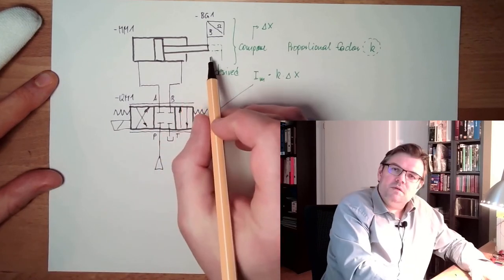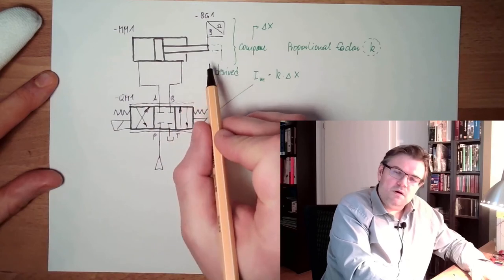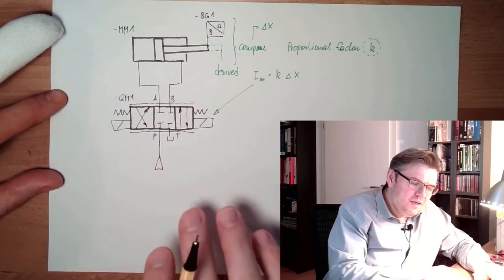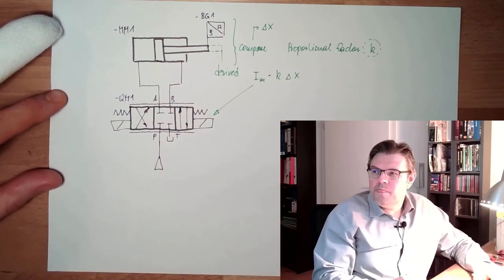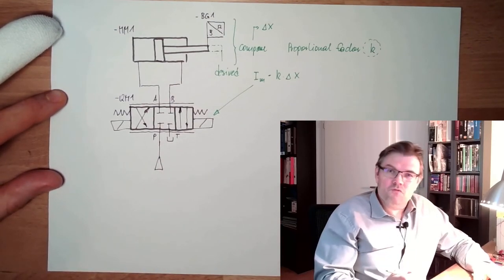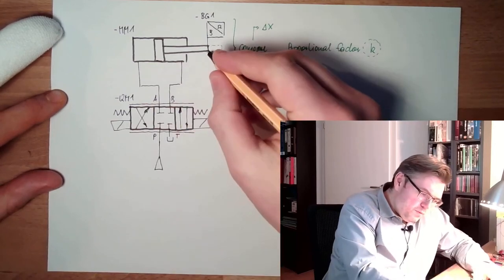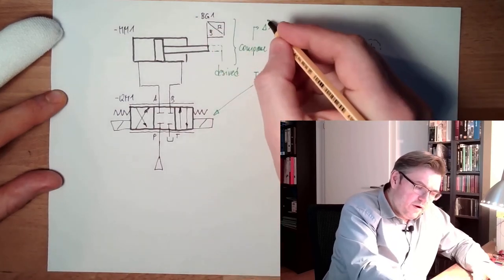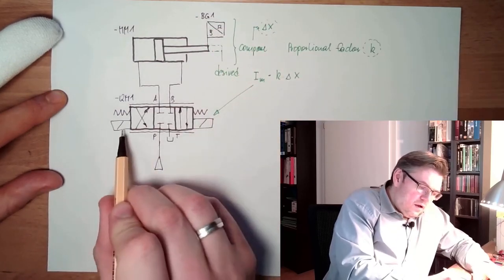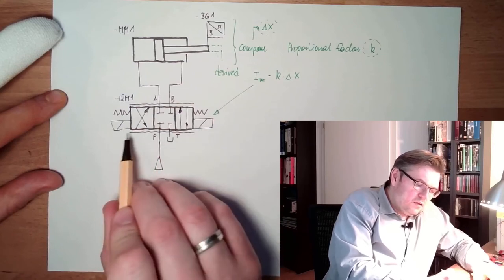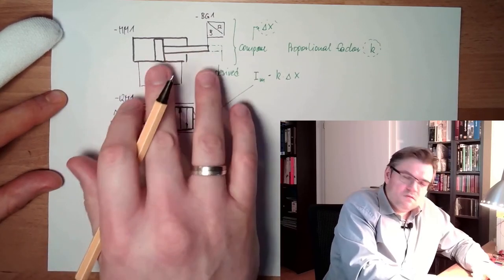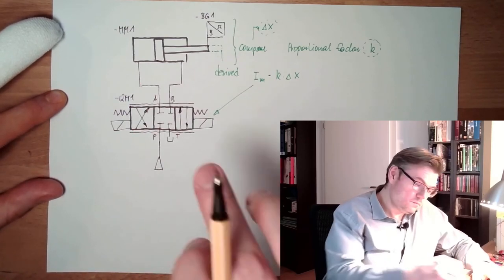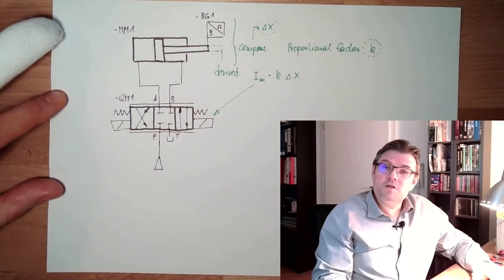And the further I go to the desired position, at exactly the desired position we will have middle position. We will probably stop a little bit before because then it's just leakage oil or something like this. So this is a position control loop. Measure position, know where we want to go, depending on the difference, adjust the magnetizing current of the proportional valve and let the cylinder move.